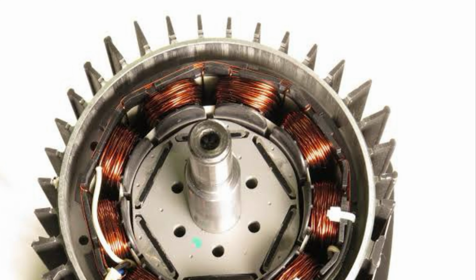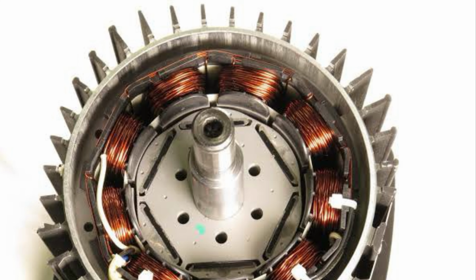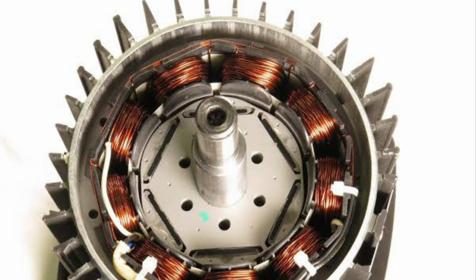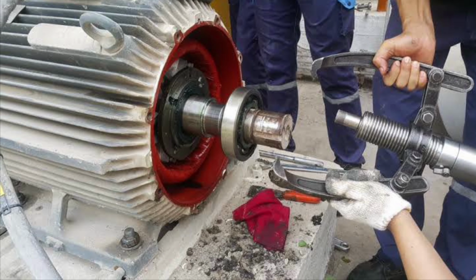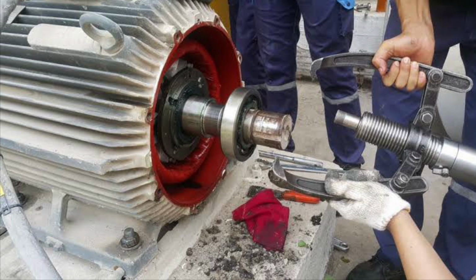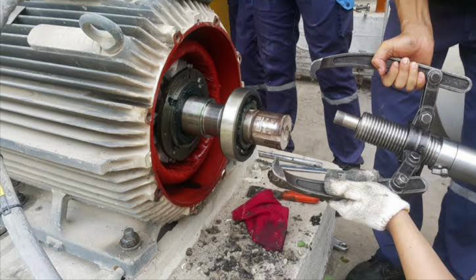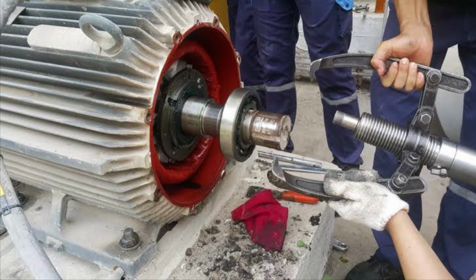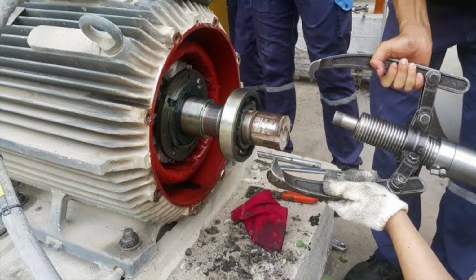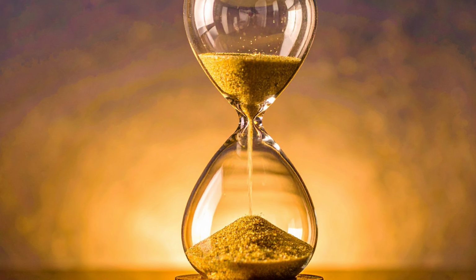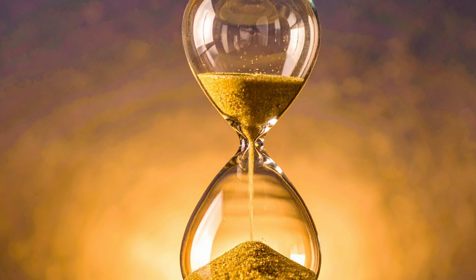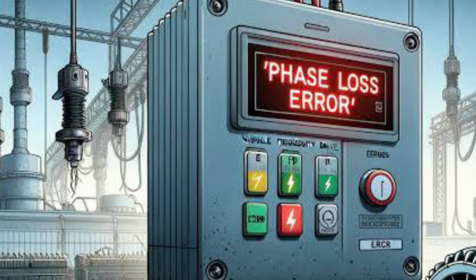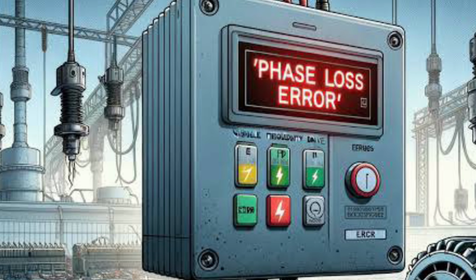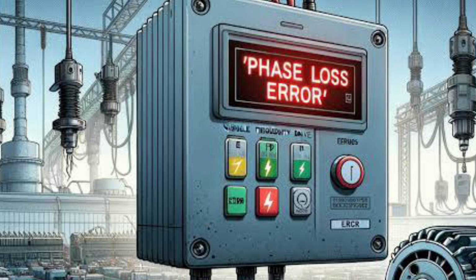This device has a current-based dry run protection. If the motor runs without water, then it takes a lower ampere than its load ampere. This device stops the motor in dry run condition and protects it from burning. This device also has an on delay timer, off delay timer and cyclic timer, and a dry run reset timer is also provided. In this device, SPP is provided.